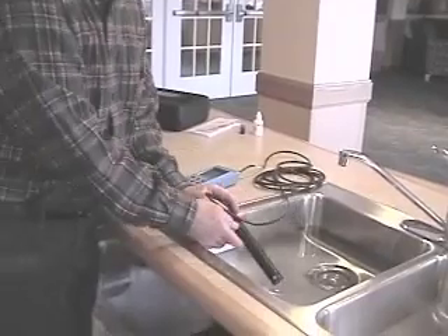Now, if you feel more comfortable, if you're in areas with a lot of turbulence and the flow is really great, and you want more protection for your membrane cap, you can leave this protective guard on and run your water samples that way. That will still work, and it'll give you more protection. After completing the initial DO monitoring, if you are traveling to another site or multiple sites, you should turn the meter off, because you have a lapse in time between sample sites and your altitude will probably change. So at that time, once you get to your next site, you'll need to recalibrate.